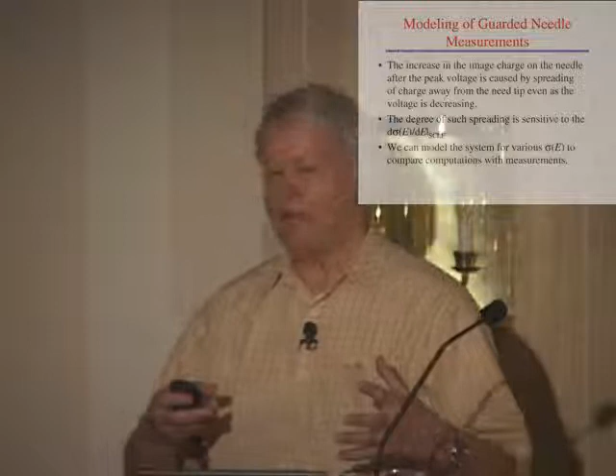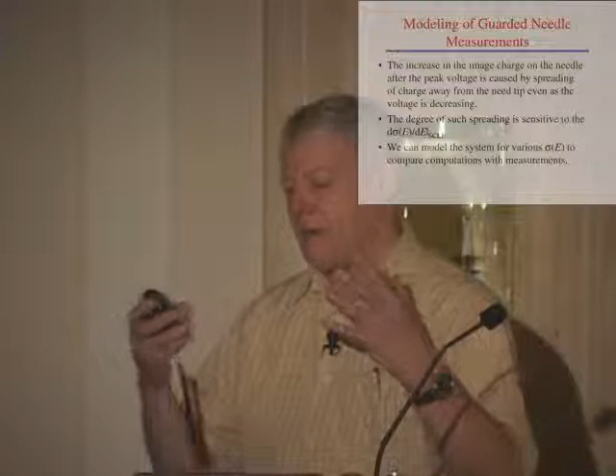Basically, what's happening here is that even though the voltage is going down, the field's going down, of course, the carrier mobility is not going instantly to zero. So the charge is continuing to spread away from the tip, even though the field's going down. And this gives us insight into how the carrier mobility or the conductivity changes with field in this very high field region. So we can, for example, do transient nonlinear finite element calculations and compare them with the measurement. So here's the measurement, and here's a calculation for an exponential of kE, kE to the 1/2, kE to the 1/3. And if you look at these, it appears that the 1/2 fits best with the measured data. But certainly n is less than 1 and probably greater than 1/3, somewhere in the range of 1/2.